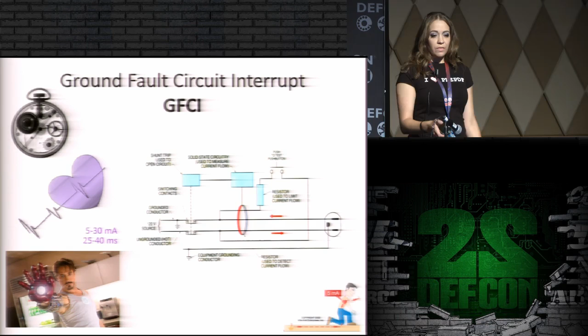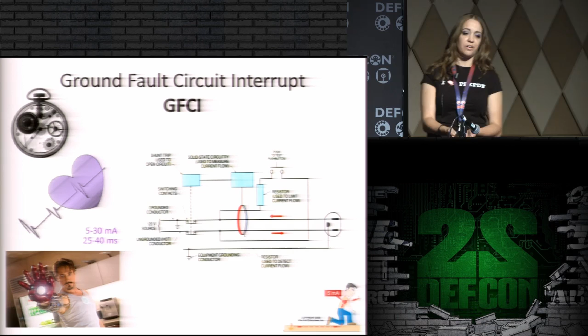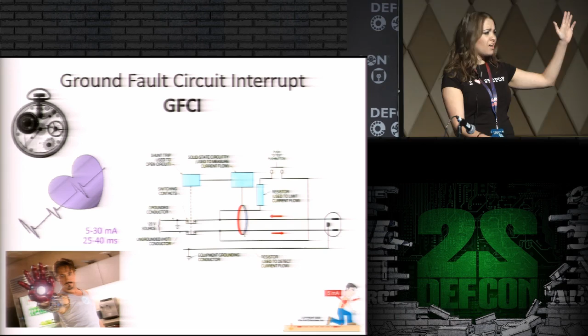But in the little toroid there's also the hot, the neutral, and an extra one for the test button. If you push the test button, it enables that third line, which imbalances it and causes a trip. That's what you're supposed to do to test the GFCI mechanism is actually working, and they recommend testing it often. But how many of you test your GFCIs often? Very good, I'm super impressed.